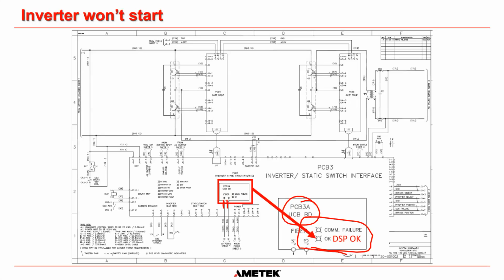Unfortunately, I don't have a video to show you, so it's a little bit ambiguous when I say you should get fast blink. But basically, if it's blinking at about once a second or once every half second, then that's slow blink. Something is wrong and the software hasn't loaded correctly. Fast blink is where it's blinking maybe 3 or 4 times a second. And there is quite a difference. If you don't get fast blink, the inverter will never, ever start, no matter what you do.